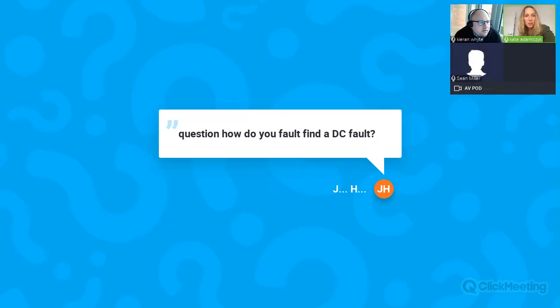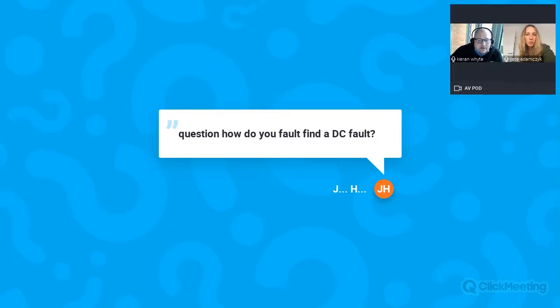A question there that James has asked regarding RCD technology: how do you fault find for DC faults? It is a difficult one. You can fault find for AC faults easy enough. You've got your multi-function tester, you do the megger test. It's one for the industry who make the testers. To be honest with you, if you look at a tester these days compared to 10 years ago, you wouldn't have a lot of the applications on it that you can do. A lot of testers have facility for testing EV circuits. So I think for us, that would need to be pushed back to maybe the regs or even the manufacturers of the test equipment.